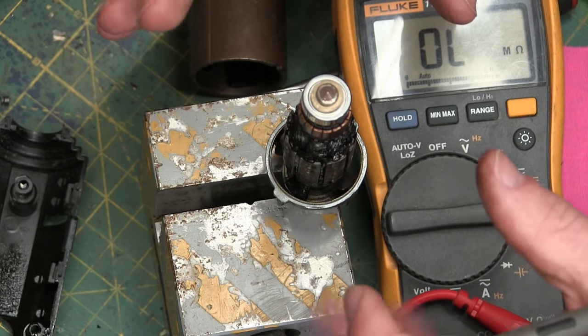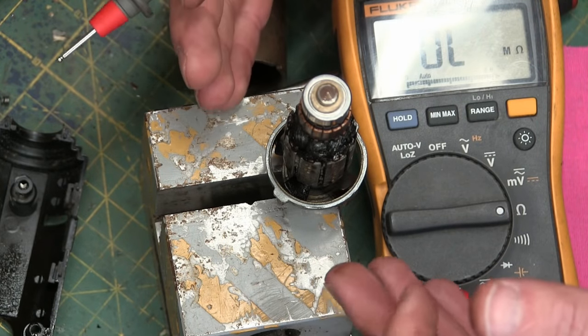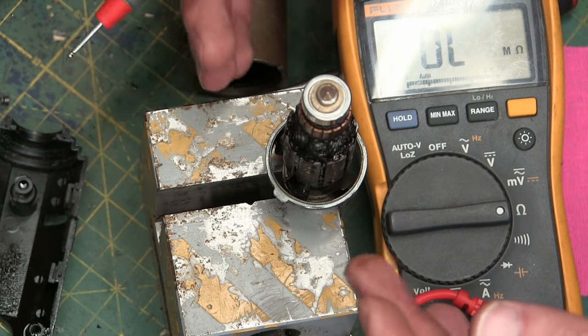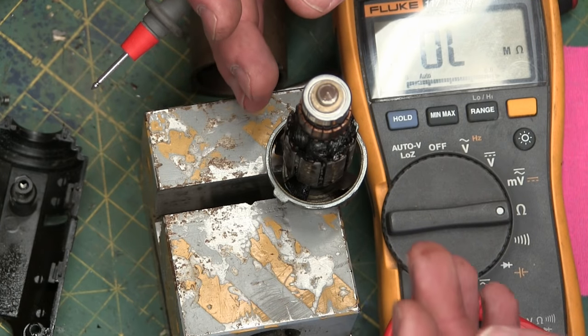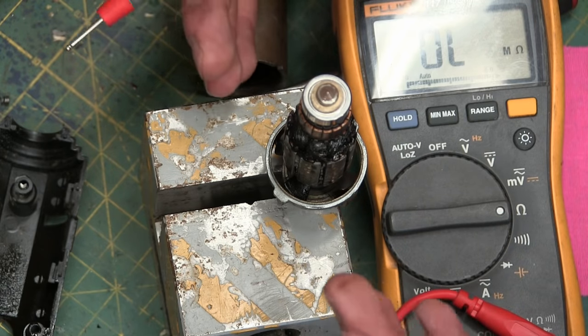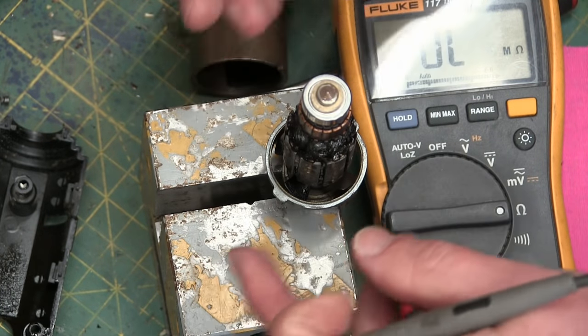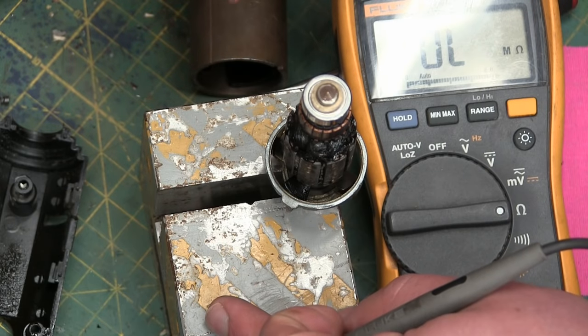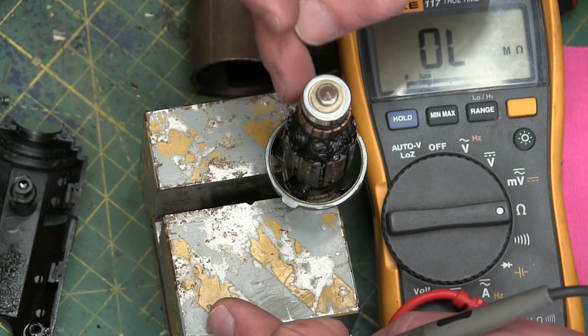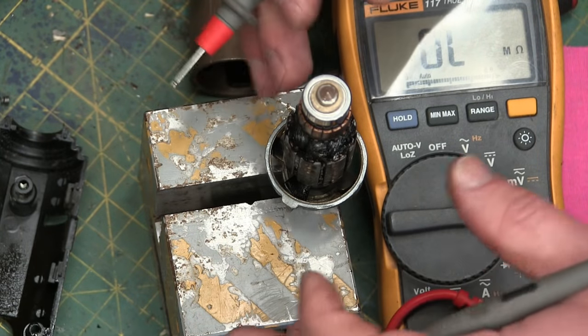In days bygone there would have been places, motor rewind shops, all over. Every little town would have a motor rewind shop that would do alternators for your car and starters. Of course now starters and alternators are throwaway items. You bring it back to the wholesaler. They give you $30 core charge and you get a new one. You stick it in there for a hundred bucks. It's not worth rebuilding. Nobody can make a living at it. But in those days they used to have a device called a growler which was essentially a bunch of laminations and it would just pulse a magnetic field and it would make this thing vibrate. It would induce a voltage in the coils so you could see if any coils were bad or weak or so forth.